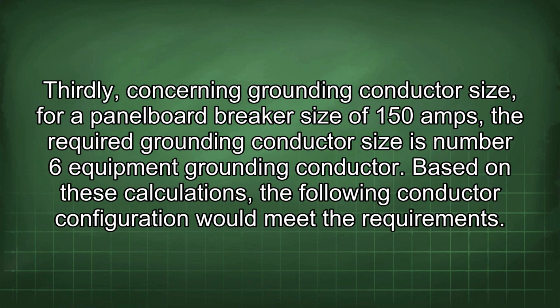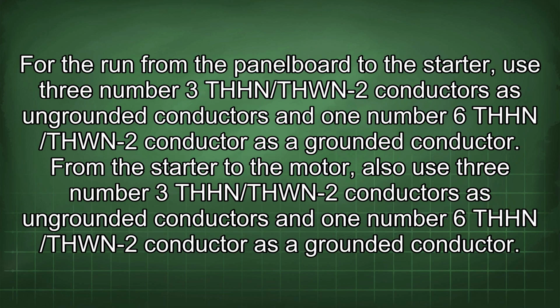Thirdly, concerning grounding conductor size, for a panel board breaker size of 150 amps, the required grounding conductor size is number 6 equipment grounding conductor. Based on these calculations, the following conductor configuration would meet the requirements. For the run from the panel board to the starter, use number 3 THHN/THWN-2 conductors as ungrounded conductors and number 6 THHN/THWN-2 conductor as a grounded conductor.